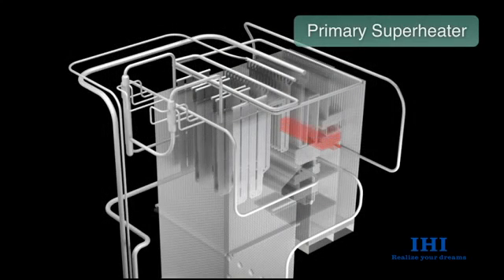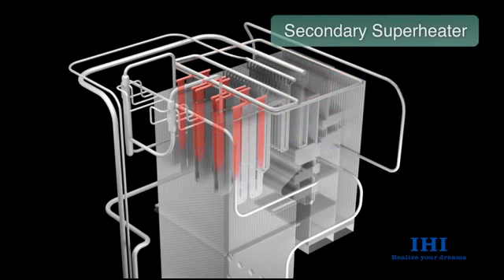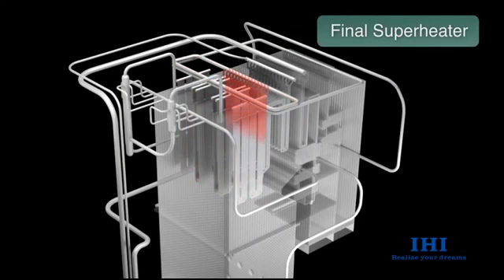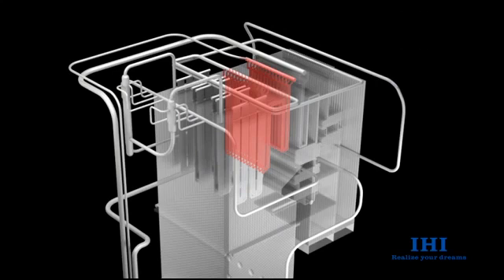The superheater consists of three sections. The steam is passed through the primary superheater, secondary superheater, and final superheater, exchanging heat with the combustion gas. Increasing the steam temperature at the superheater outlet makes more efficient power generation possible.